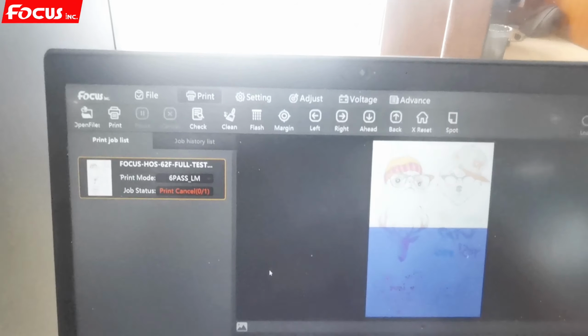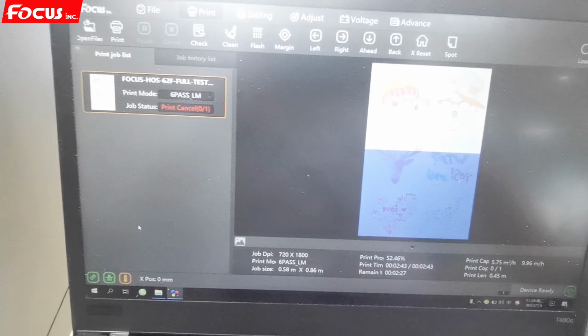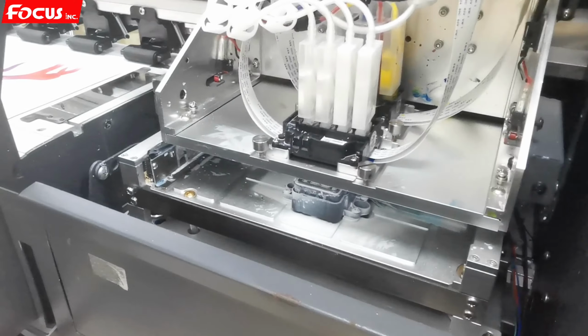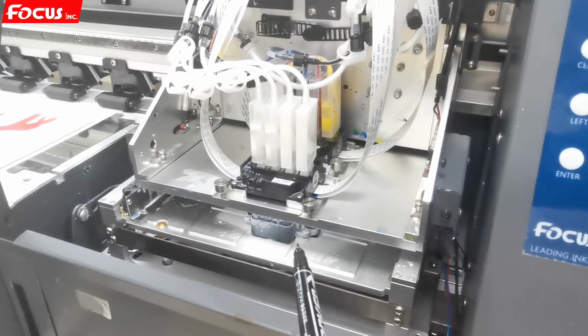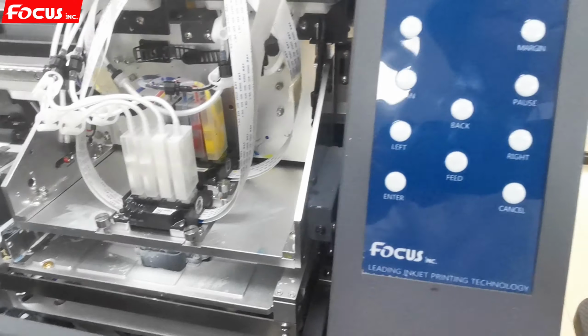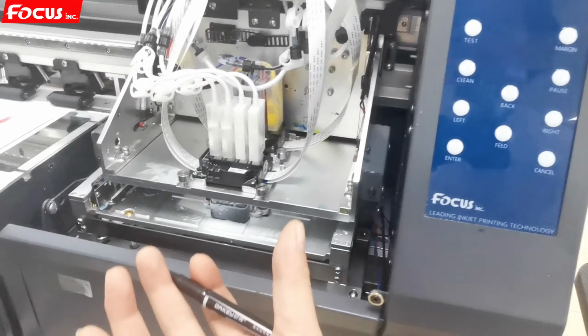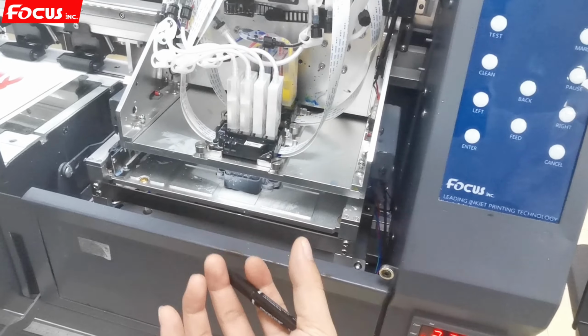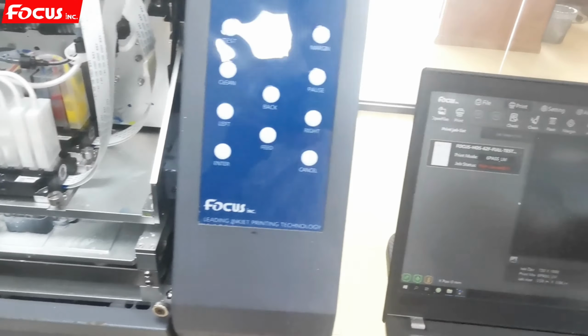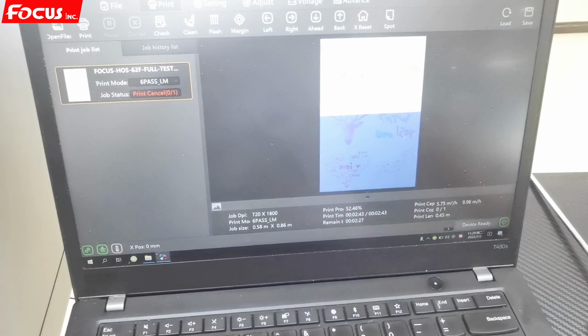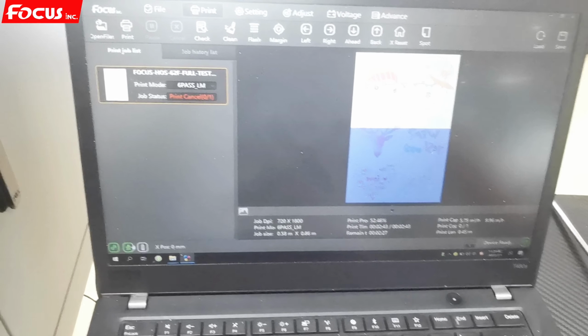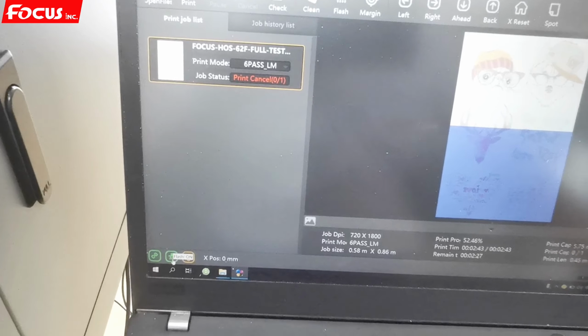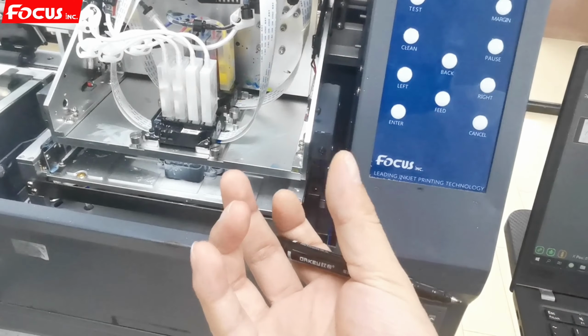And right now, if you are not printing for a long time, you must fill the clean solution into the cap station and close the software to make sure the cap station surrounds the print head. But if you just go out for dinner for several hours, we need to open the flush from here, to be sure the flush is on. We open the flush here to make sure the print head can flush a little bit of ink out to prevent head clog.